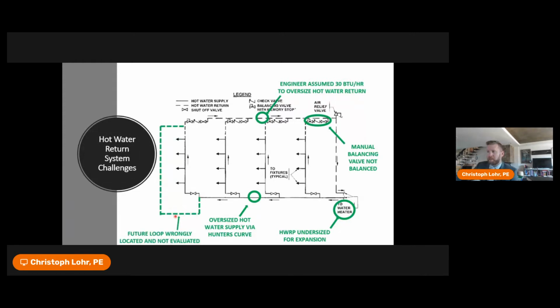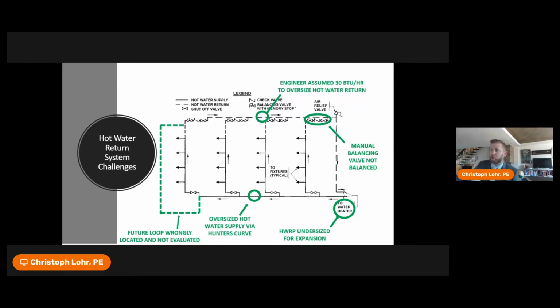One of the other issues, though, is a lot of times, especially in hospitals, as projects are retrofitted, you have future loops that are either wrongly located, so you have them tying in upstream of a balancing valve, or they're not even part of the hot water return evaluation as a whole. And so the pumps end up becoming undersized. So a whole host of issues can occur as a result of improper design, but then you compound that with the installation issues. Actually, installation tends to not be the issue, but sometimes it is. But the commissioning and balancing that doesn't happen, and then owners not going back and doing a whole system evaluation, or engineers not going back and doing a whole system evaluation during reconstruction or during renovation or addition work. It just compounds the issue.